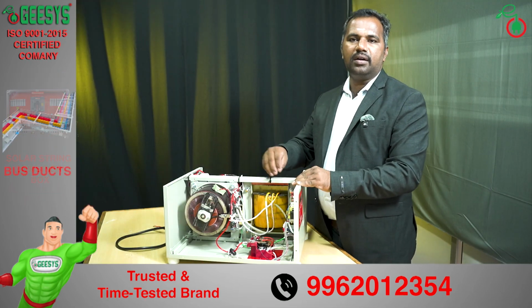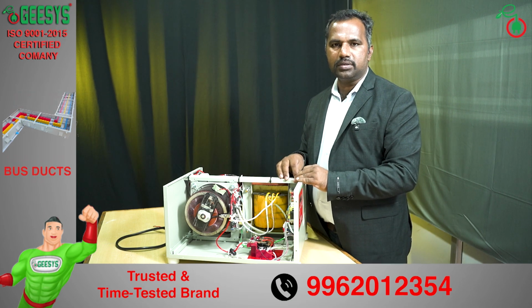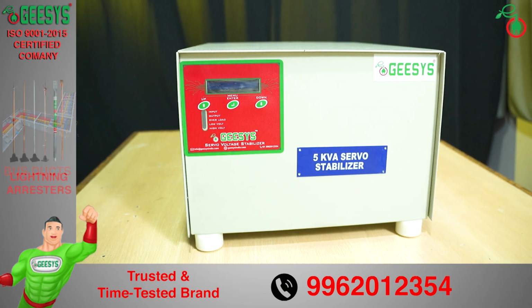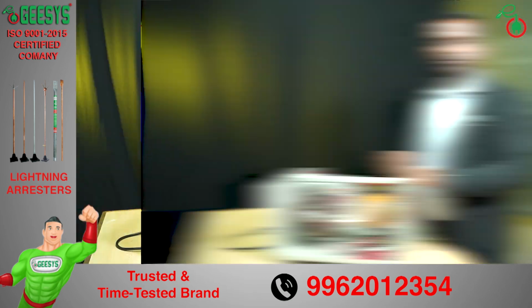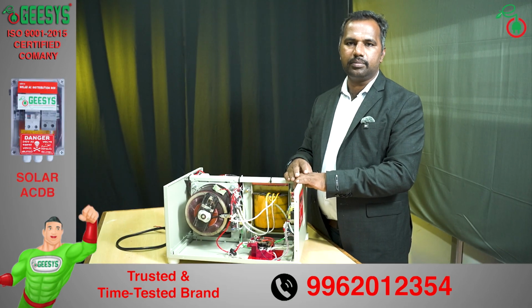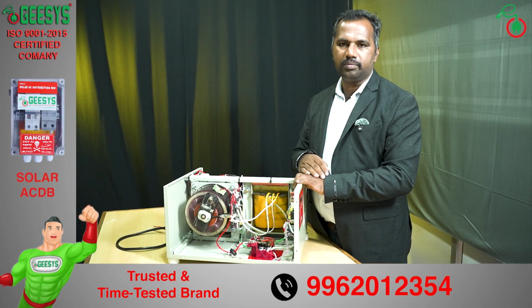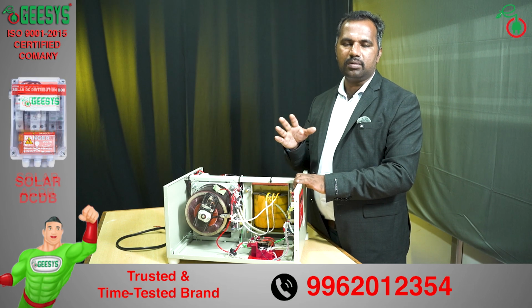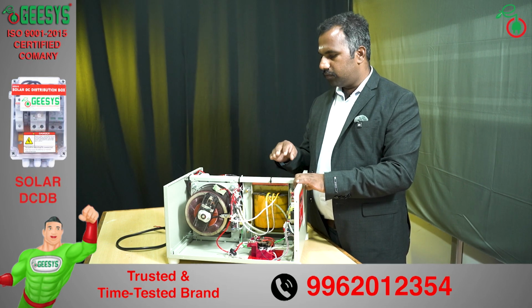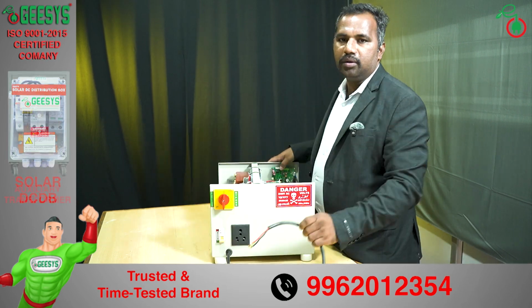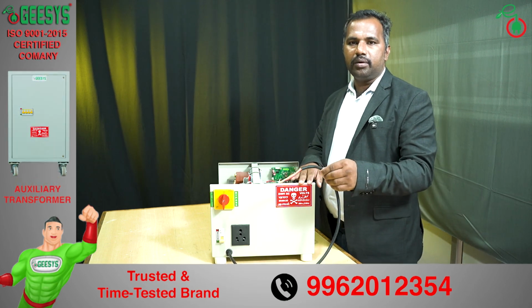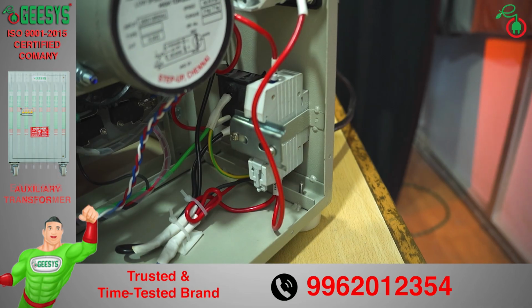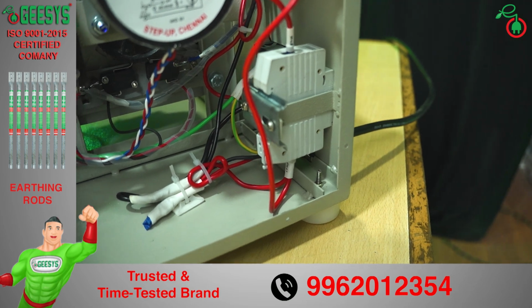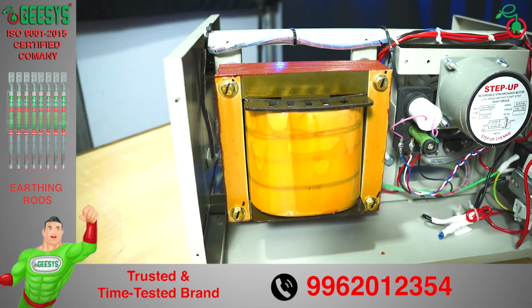This is the internal view of the servo voltage stabilizer. This 5 kVA servo stabilizer majorly has 9 components. We will show you the working principle and the components of the servo stabilizer. I'll explain them one by one. This is the input cable. This cable is connected to an MCB. The MCB takes care of the safety of the servo stabilizer. Through the MCB we are getting power to the transformer.